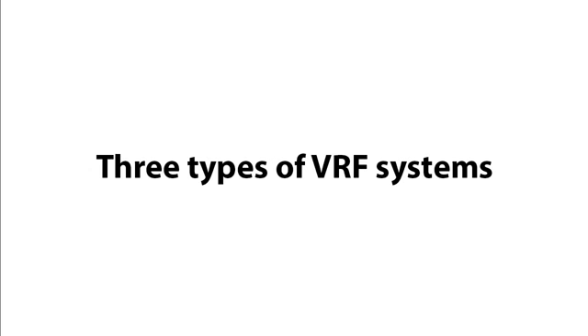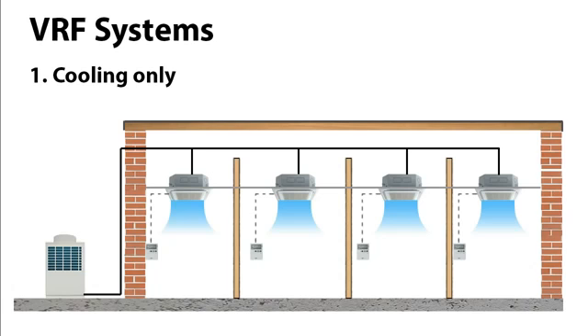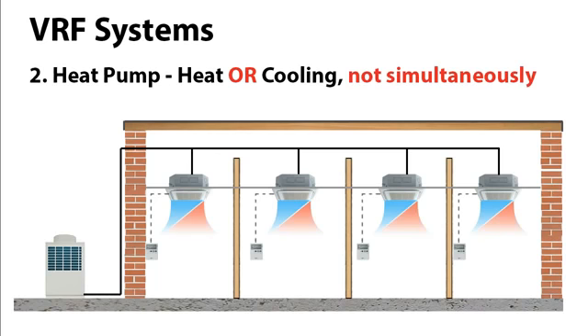So there are three main types of VRF systems. The first one, and the simplest version of this, is the cooling only VRF unit, where all units can only provide cooling. The second type of VRF unit is the heat pump, and this is where all the units are again for different zones, but they can only provide heating or cooling. They cannot provide both, well, simultaneously at least. You have to change the system over to provide heating or cooling, and all of these units together will provide heating or cooling at the same time.